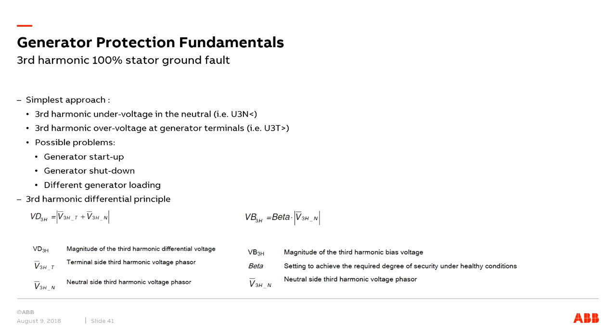Okay, so the more effective way of sensing or providing 100% protection is a third harmonic differential principle, where we have a differential voltage calculated between the third harmonic content from the neutral side and the terminal side. And then, of course, it has a bias characteristic with the magnitude of the third harmonic bias voltage.